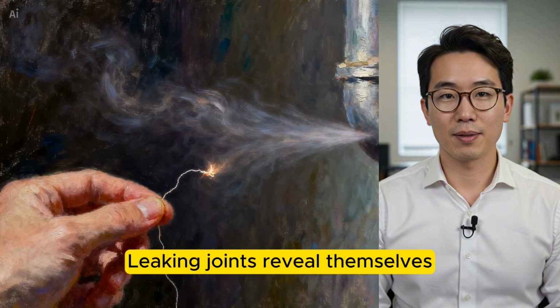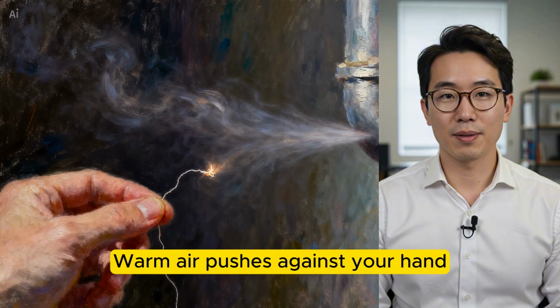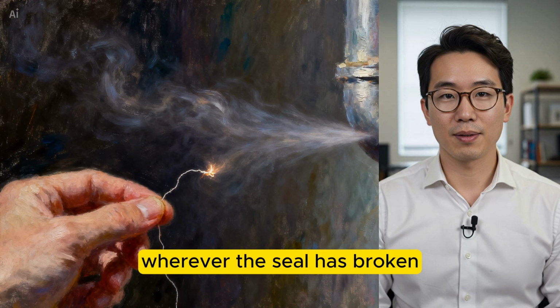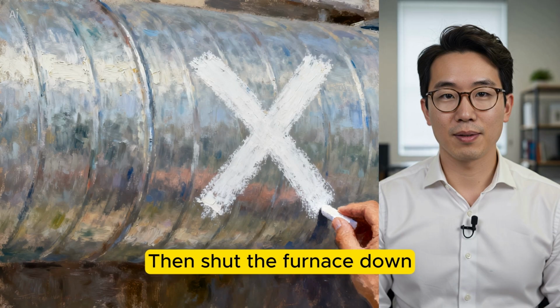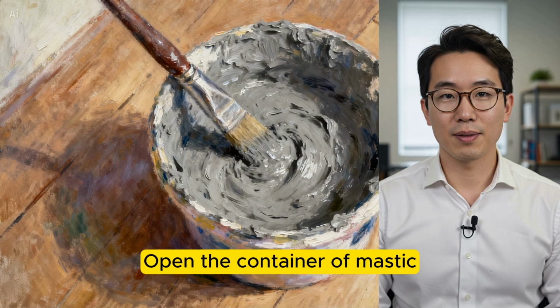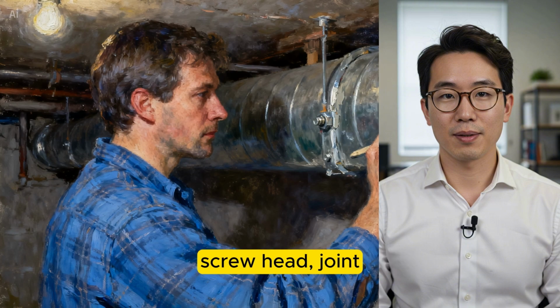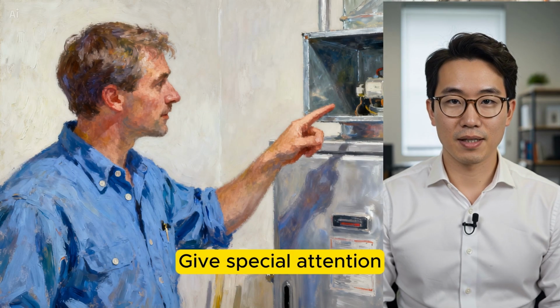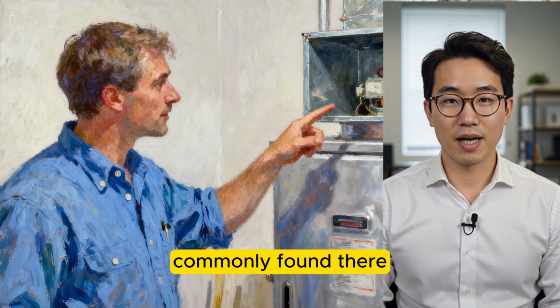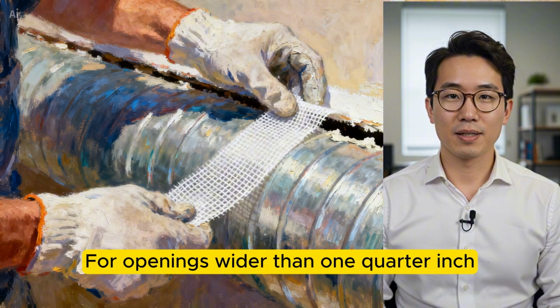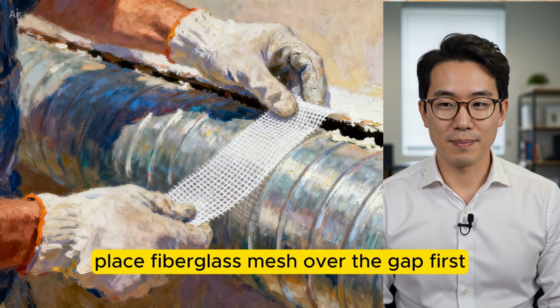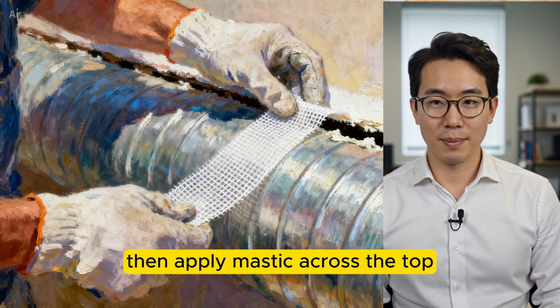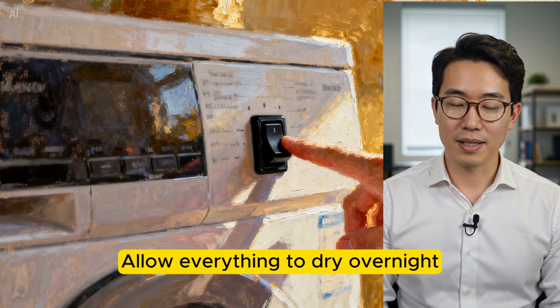Leaking joints reveal themselves immediately. Warm air pushes against your hand wherever the seal has broken. Mark those spots with chalk. Then shut the furnace down. Open the container of mastic. Dip the brush into the paste. Spread it over every seam, screw head, joint, and connection point. Give special attention to the plenum because the largest leaks are commonly found there. For openings wider than 1/4 inch, place fiberglass mesh over the gap first, then apply mastic across the top. Allow everything to dry overnight.